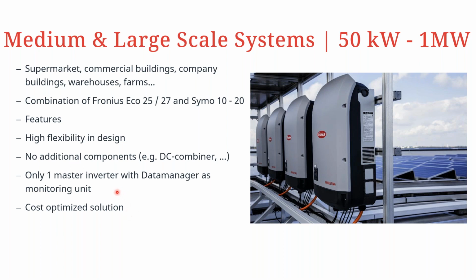And only one Data Manager will be required for every, let's say, a couple of inverters in the Solar.net ring communication loop. Those who have dealt with Fronius inverters know that you do require a Data Manager for data communication to Fronius Solar.web, as well as for things like export limitation or energy management within the Fronius inverter. So one Data Manager would be required for every communication loop, or what we refer to as the Fronius Solar.net communication loop.